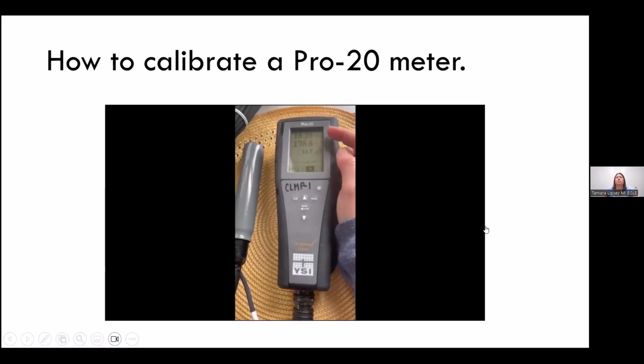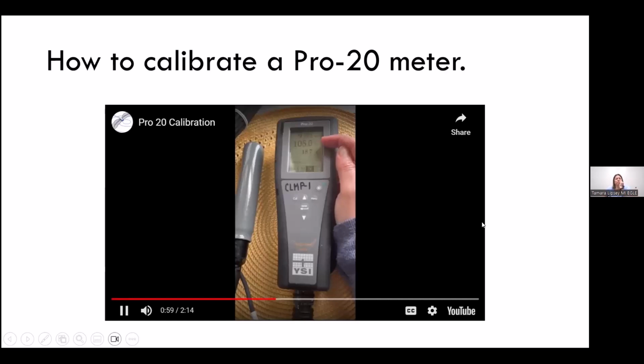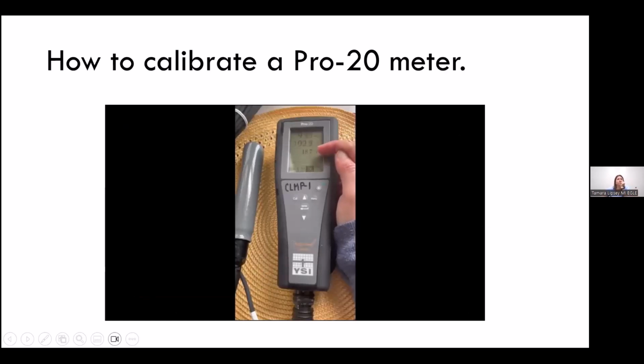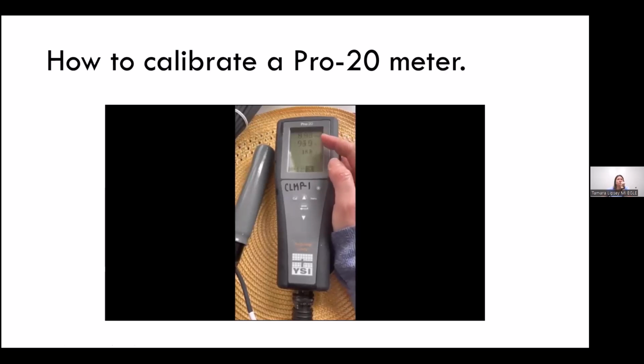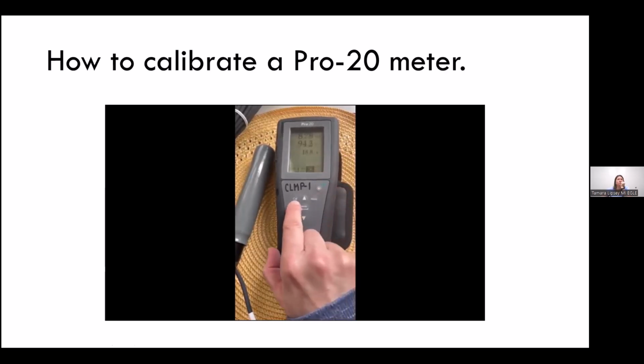You'll see at the top here, there's two measurements. One says milligrams per liter, mg/L. One says percent. The percent is the percent saturation, how much oxygen is in this container right now. And then the milligram per liter is what you'll be measuring when you put the probe into your lake. The temperature units are in degrees Celsius, which is what you want. And to calibrate, really all we have to do is hit this button here, press it, and then hold for about 3 seconds.